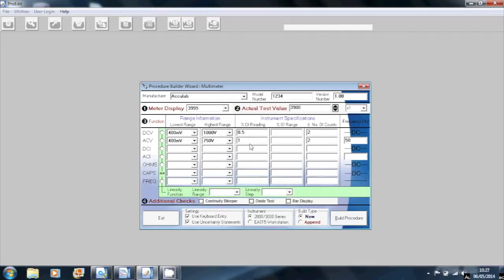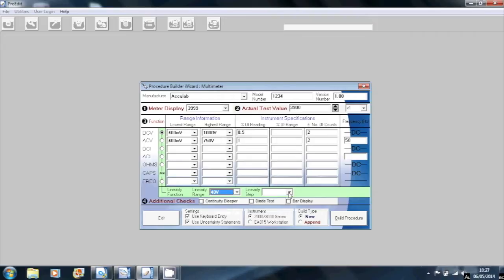I'm also going to select a linearity range of 40 volts DC with steps of 10 volts. As you can see, I've written this example procedure very quickly. I'm now building the procedure and preparing to open it in ProCal.